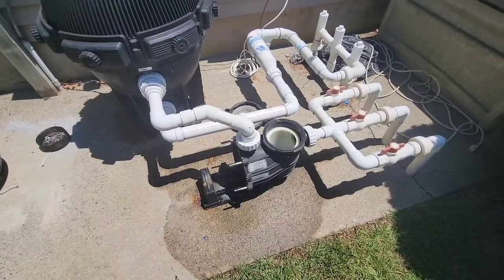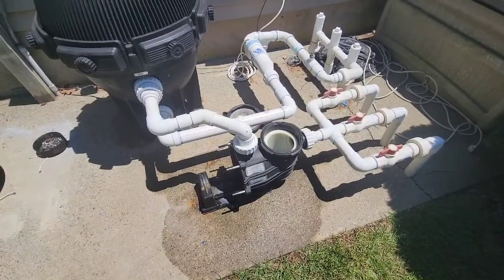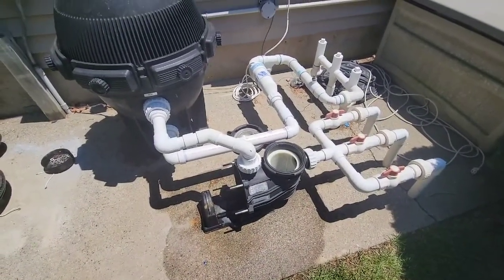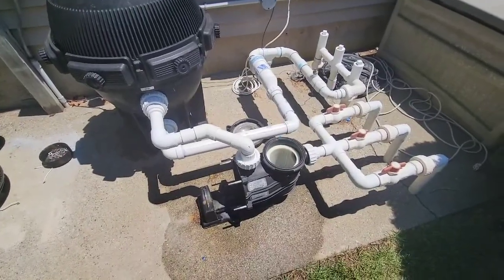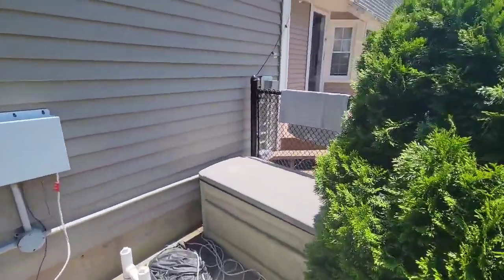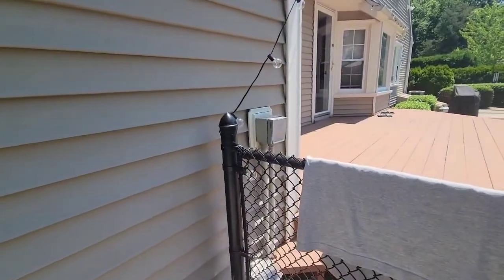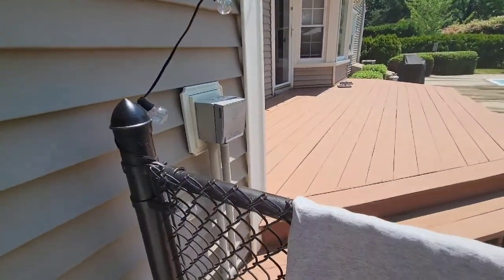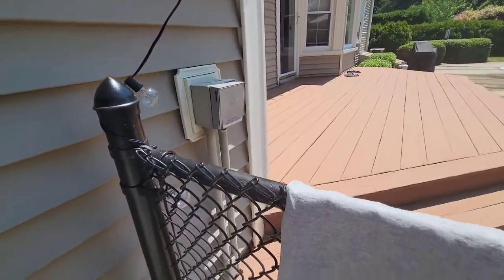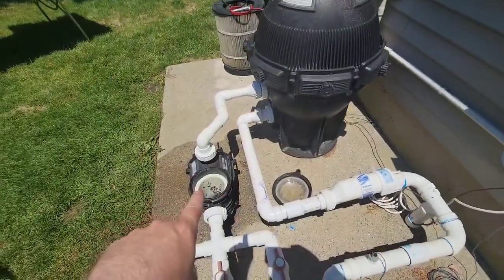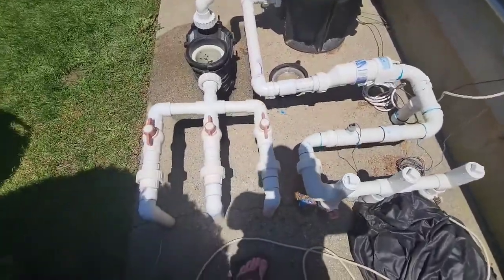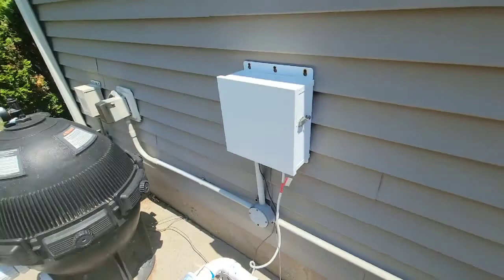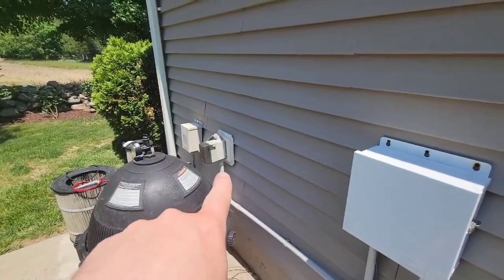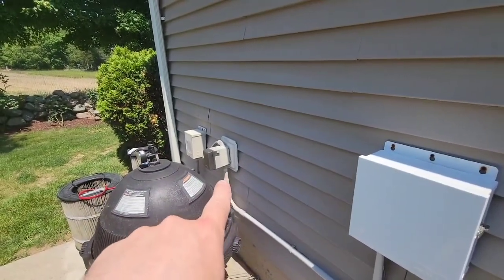But that was just one issue. The main issue originally was that he had reported losing pump power via the switch on the wall. I'm going to walk you through the electrical stuff in a second, but he's got the pump powered separately through a homemade cable to an always-on receptacle down here, because the pump receptacle has lost power.